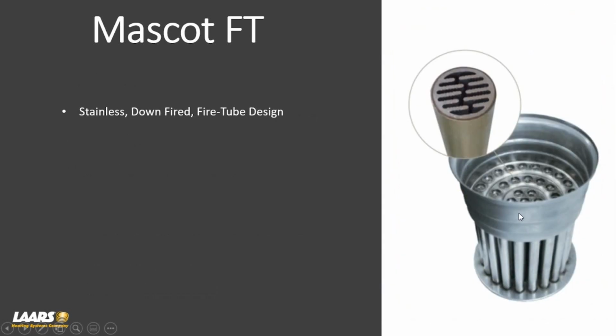Now, a little bit about the heat exchanger. This is an all stainless steel, welded, 3/16 stainless steel heat exchanger, and it's a fire tube design. So we have a burner up top, firing, and heated flue gases travel down these tubes, down to a flue collector on the bottom, and then up and out your vent.